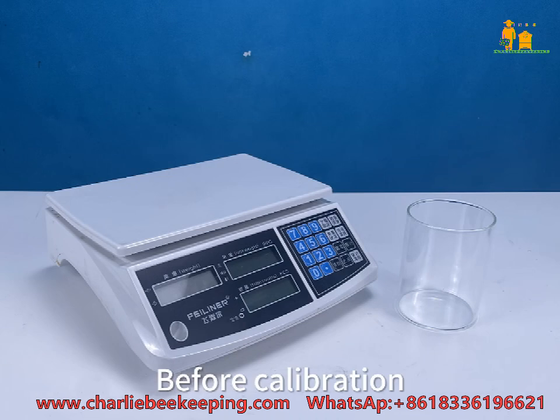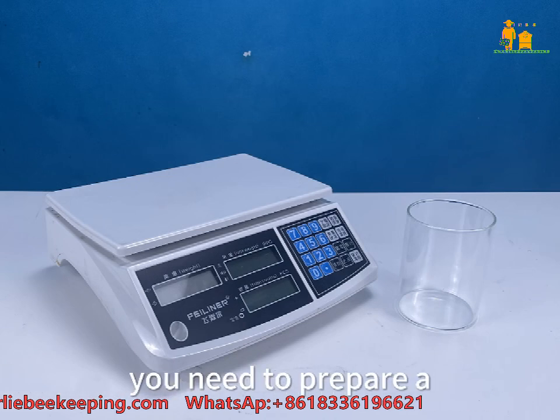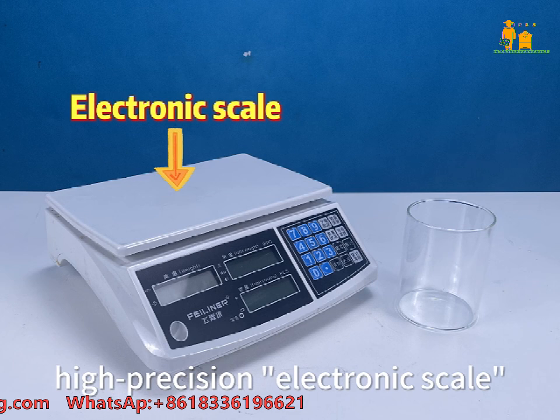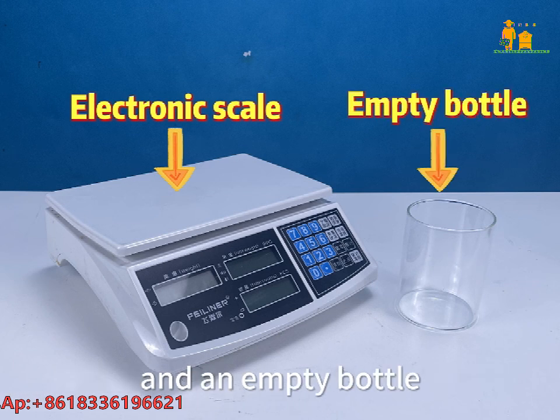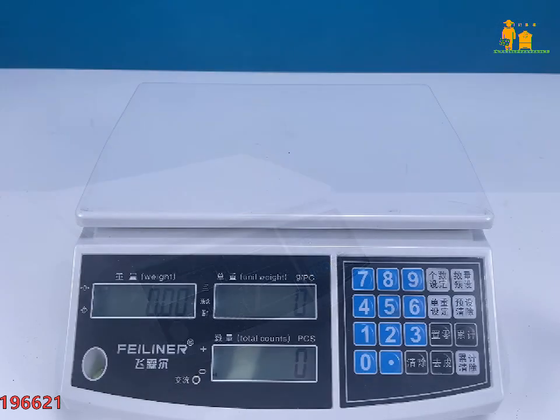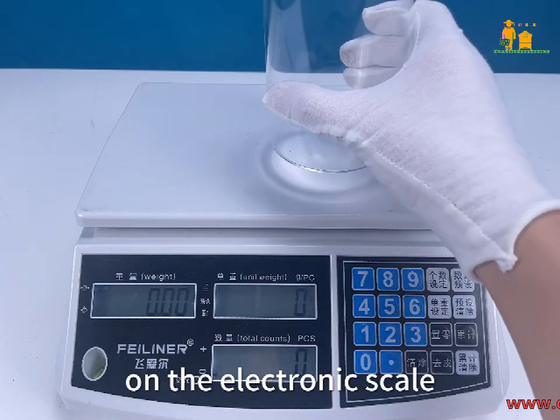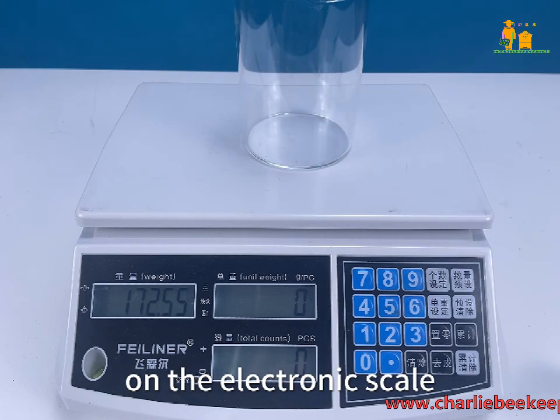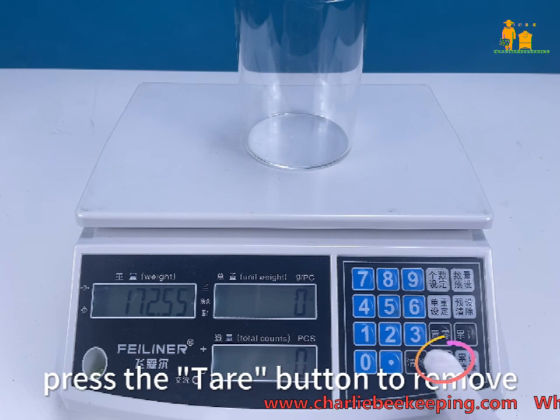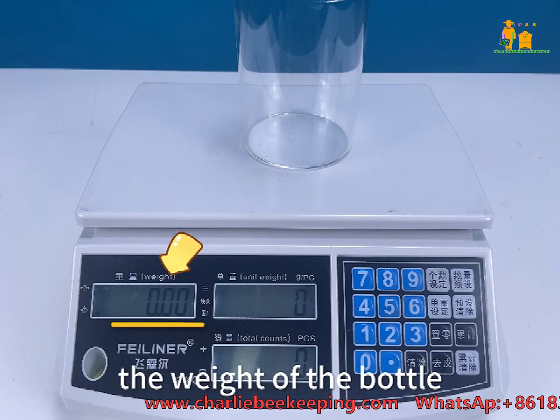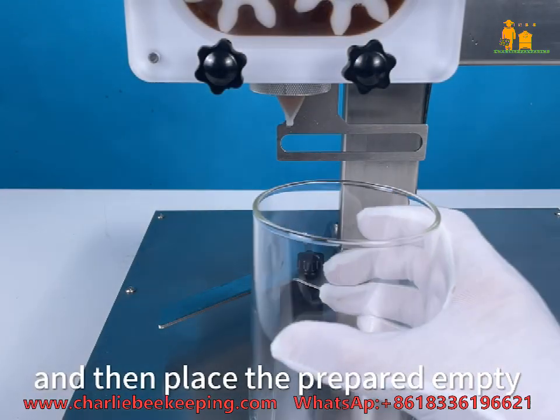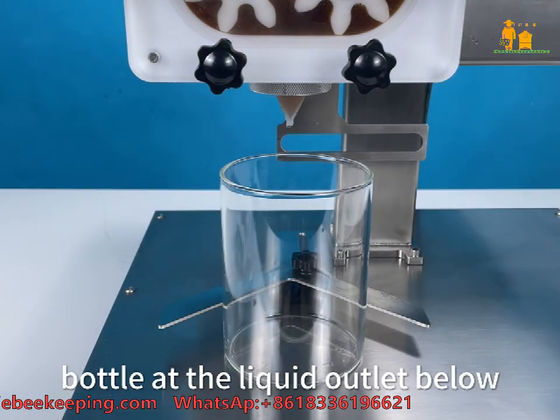Before calibration, you need to prepare a high-precision electronic scale and an empty bottle. Place the empty bottle on the electronic scale. Press the tare button to remove the weight of the bottle. And then place the prepared empty bottle at the liquid outlet below.